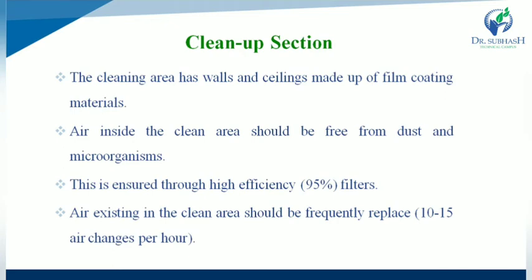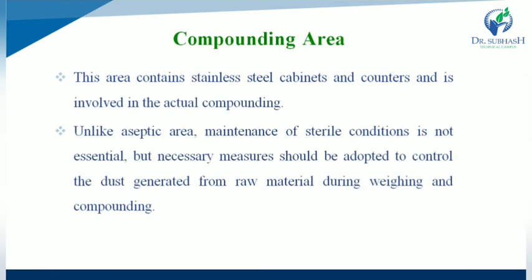Air that is used in a cleanup area is frequently replaced, 10 to 15 air changes per hour. That is regarding the cleanup area. Next one is the compounding area. This area contains stainless steel cabinets and counters and is involved in the actual compounding.